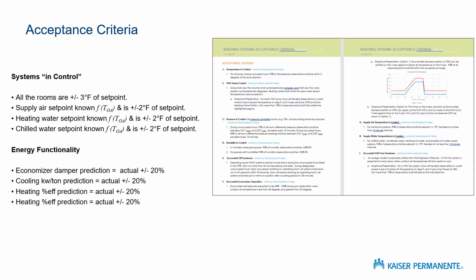As design engineers, it really has to be our job to define successful system performance. We can hire controls guys to make it come true. We can hire commissioning guys to validate it. But we, the design professionals, have to tell them what they are looking for, or else they can't go out and look for it. So let's talk about acceptance criteria themselves. There are really two types of acceptance criteria. There are in-control criteria, and then there are the energy and functionality criteria.